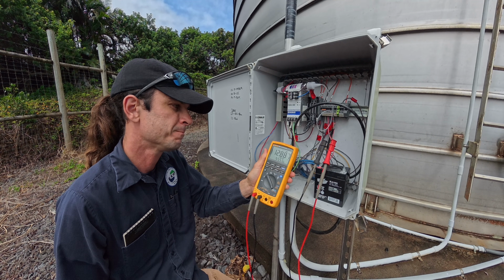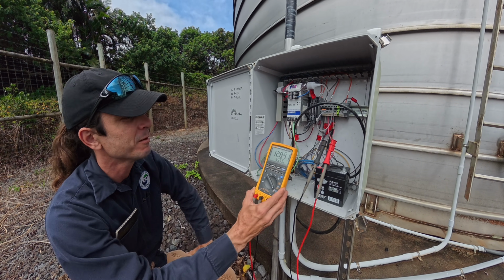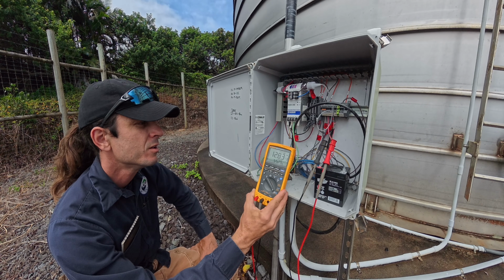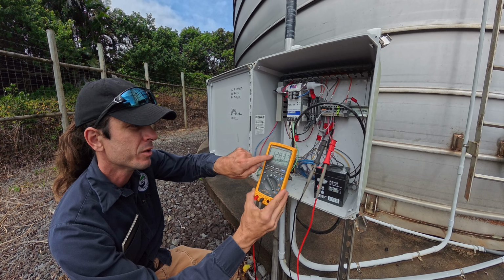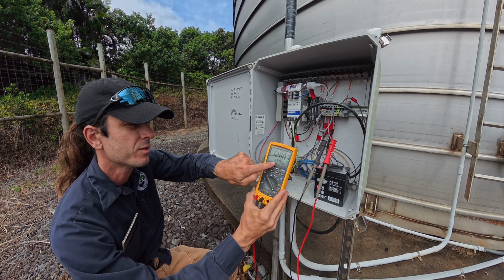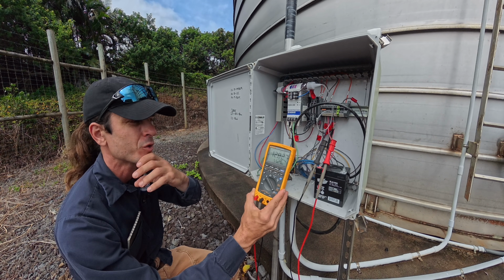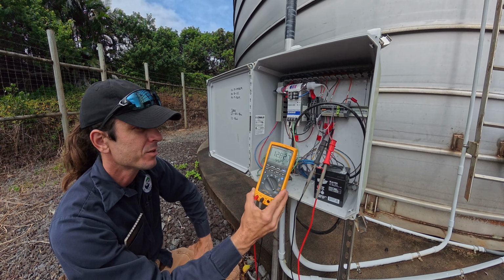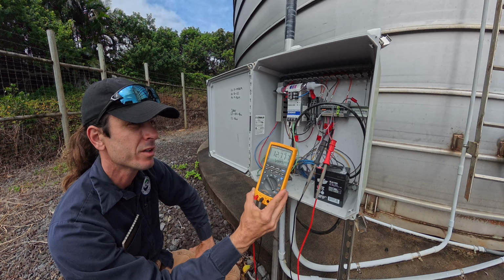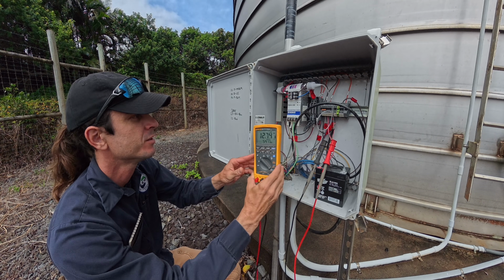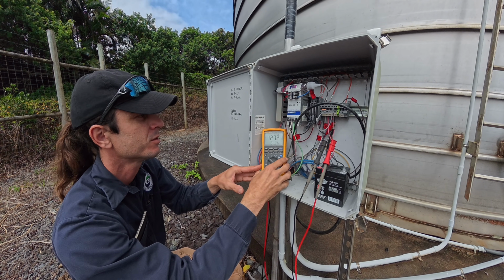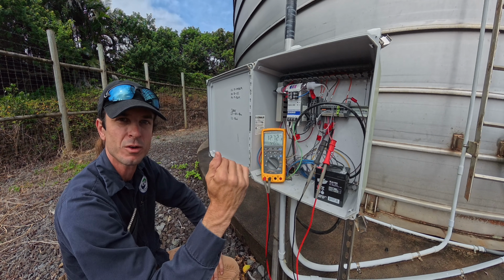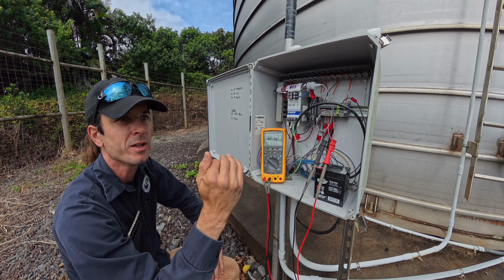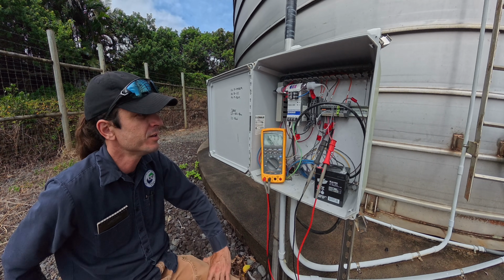It is falling. I'd be surprised if the level in the tank is actually falling that much. So this is the actual value in milliamps in the loop circuit, and this is the percentage scale between 4 to 20. So right now it's just above halfway there. I believe we're on a 23-foot transducer. Essentially, 4 milliamps would be 0 feet, and 20 milliamps would be 23 feet.